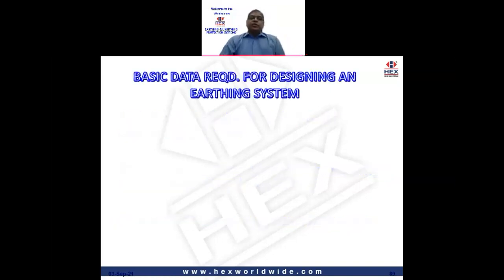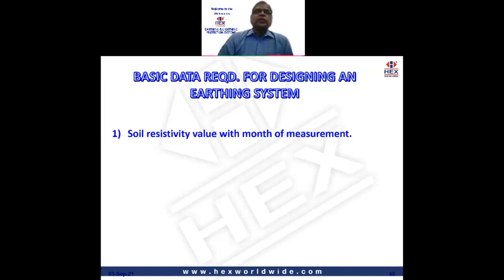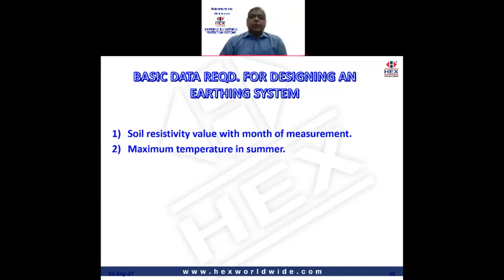The basic data required for designing an earthing system: we require the soil resistivity value with the month of measurement, and then the maximum temperature in summer. Why do we ask for the soil resistivity value with the month of measurement? Because we know the resistivity value or the earth resistance is always the worst in the summer season. So whenever we have the value for a particular month, we can extrapolate it and calculate what it would be in the summer season.